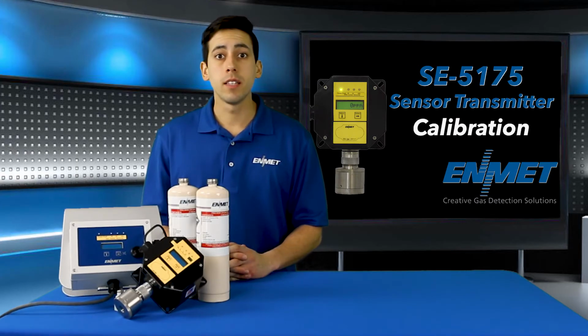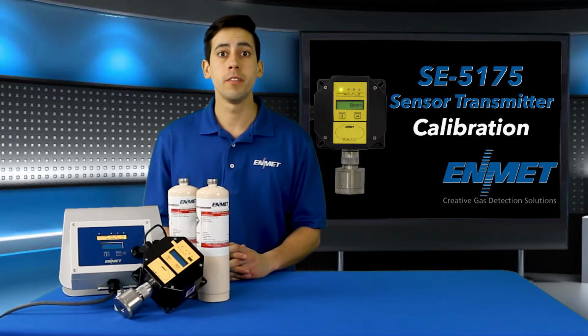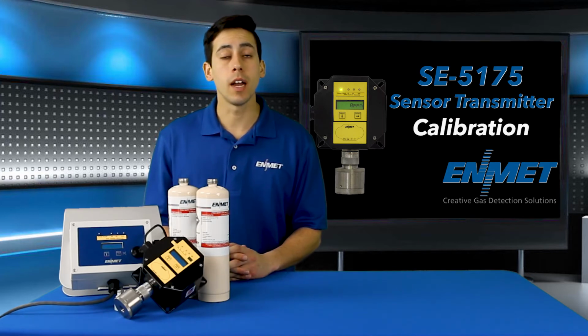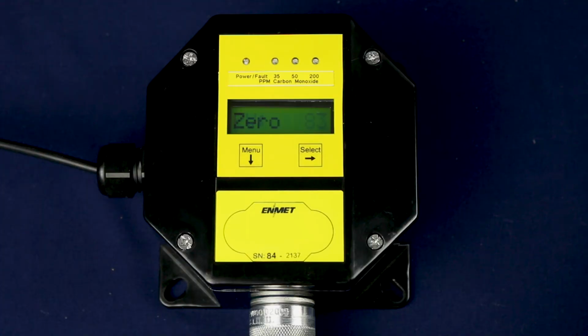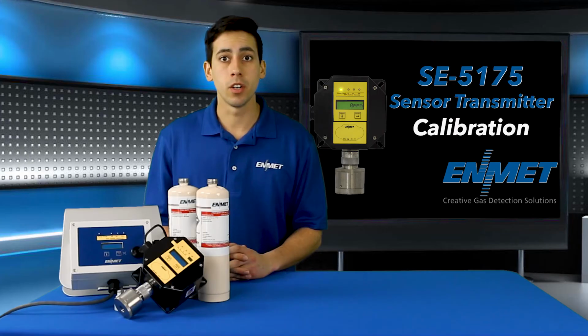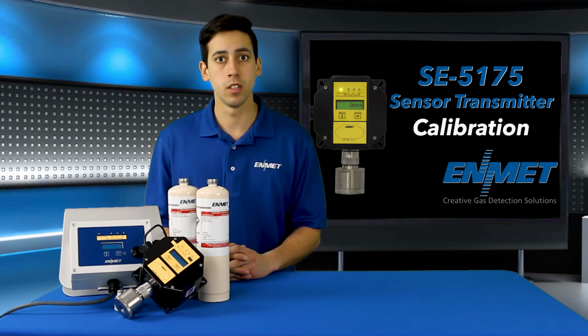If the reading did not stabilize within 255 seconds, the procedure will be aborted. If the sensor output is outside of the established safe zero parameters, the display will read bad zero. Repeat the zero procedure, making sure to use a zero gas of 20.9% oxygen.